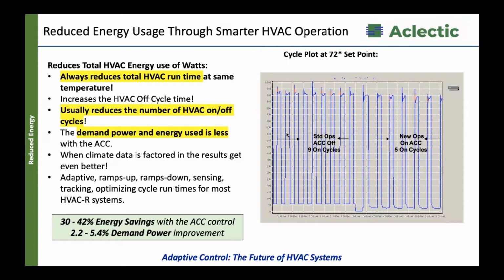Holding that same set point, changing nothing else, flicking the switch of our box that's been inserted, you now cycle on only 5 or 6 times to hold the same set point in that same space. You can quickly see we're running for shorter time, less time, and that's where significant kWh are saved, as well as the overall height of the run time being reduced. Next slide.